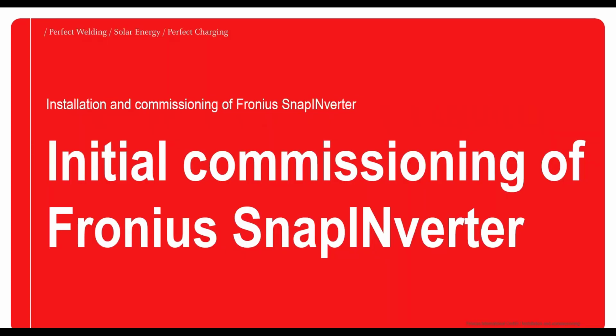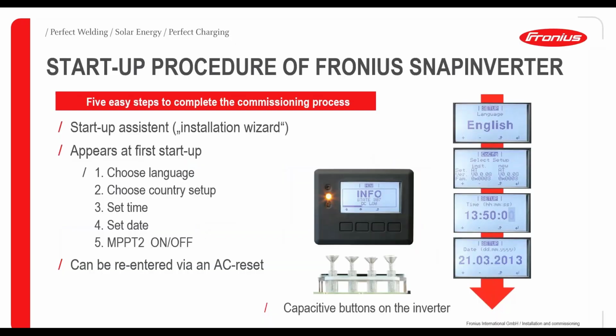After that, we want to commission the SnapInverter. It's done easily and quickly in 5 steps on the display. The SnapInverter has a display with 4 capacitive buttons below it. After we switch on AC and DC, an info box lights up and guides us through the installation wizard, which takes 5 steps. First we choose the language, then the country setup, then we set time and date, and finally we set the second MPP tracker, if we have one, to on or off. After these 5 steps, the inverter is running, producing, and feeding in power. That's all it takes to get the inverter running.